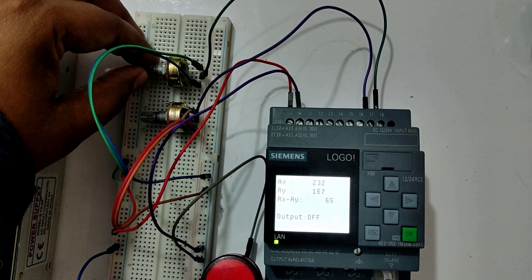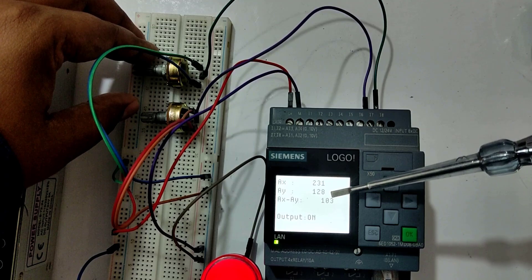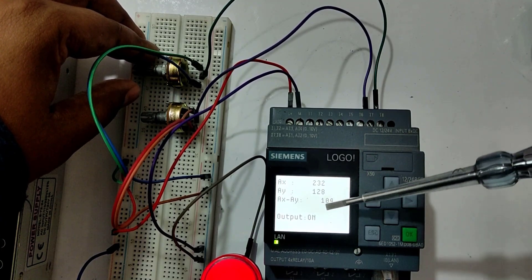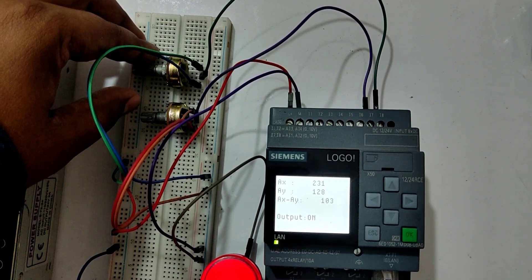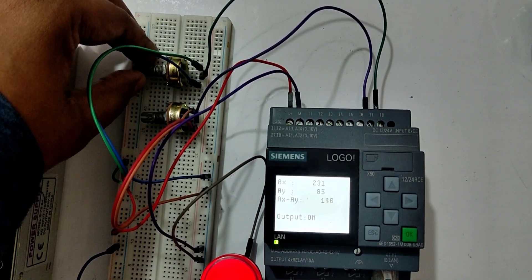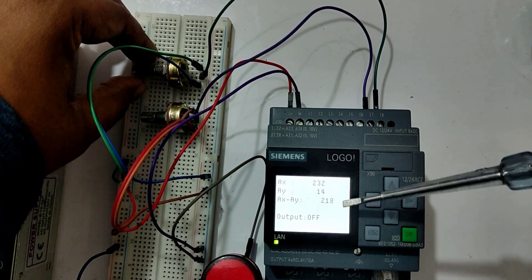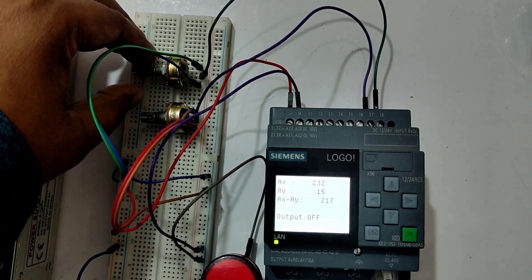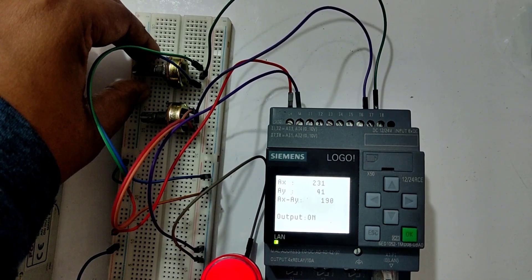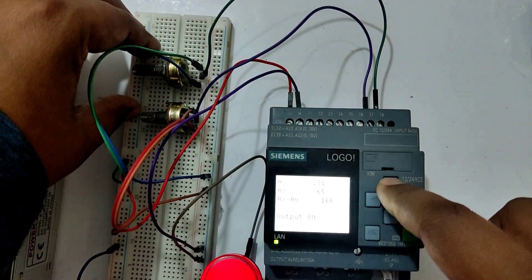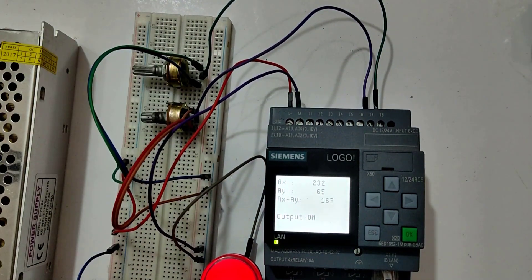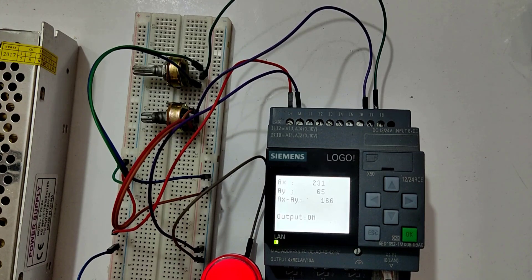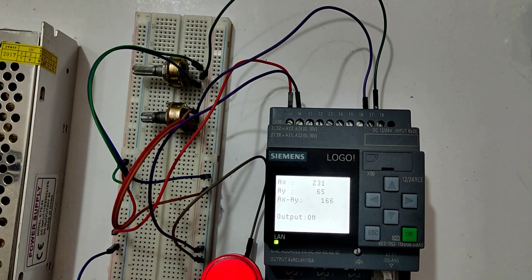You can see one is 231 and one is 128. The difference is 103. So the difference has been brought into the limit between 100 and 200. If we increase it, keep increasing, once it exceeds the 200, you can see whenever it exceeds the limit, it turns off the output. Again, if I go down into the limit, that is 100 to 200 limit, it will again turn on the light. So this is how we can use analog sensors and analog comparator block to design our program into the PLC. Thank you, see you in the next video.